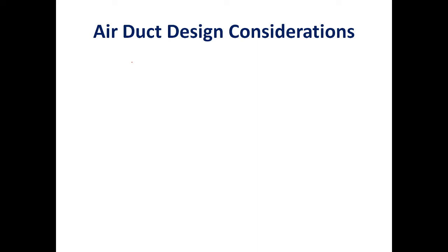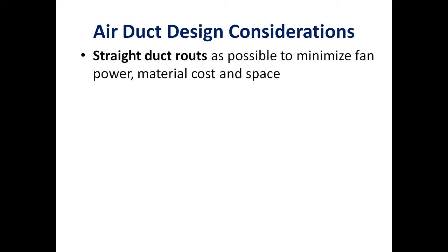Now we will discuss air duct design considerations in detail. The first consideration is that duct passages should be as straight as possible to minimize friction losses and bending losses, which results in minimum fan power and also saves material cost and space. If more bends are present, pressure losses due to bending increase, which increases fan power.